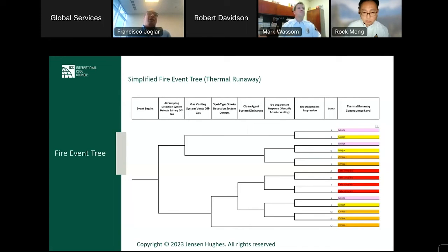At the end, you can characterize very well what type of accident you can have, where your mitigations are, what would happen if they fail, and how likely that can be. And that gives confidence that you have comprehensively covered the entire cycle of operation, right? From normal operation, to some problems in the battery that the troubleshooting person would address, to starting to see alarms that require a response and require planning with the fire brigade and fire department, to, if it's let it burn, stay at a distance, and so on.